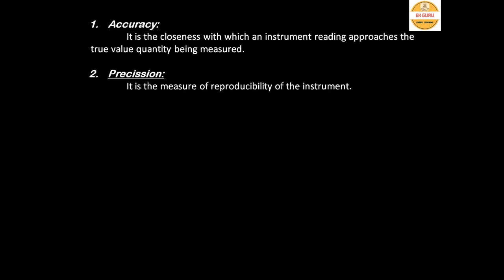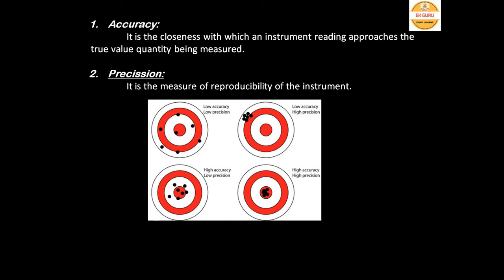The second characteristic is precision. Precision is simply a measure of the reproducibility of an instrument. To understand the difference between accuracy and precision, consider a target analogy. In the first diagram, all hits are not hitting the target — so it is low accuracy and low precision, with no reproducibility. In the second diagram, all hits are at the same place, meaning high precision, but they are far away from the target.